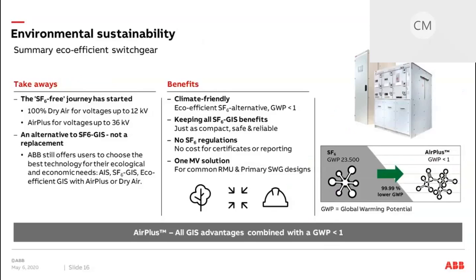Generally, AirPlus is offered in different switchgear designs for secondary as well as for primary distribution solution. And as of now, it's not a full replacement, but a very good alternative to SF6. We also have reference projects delivered to Germany and Switzerland already, and they work very well. Currently, this is the only solution that's available for ratings up to 36 kV, 2000 amp, and 31.5 kA. At the lower levels, up to 12 kV, we can also see a trend towards dry air.